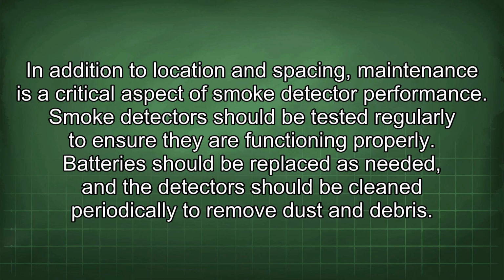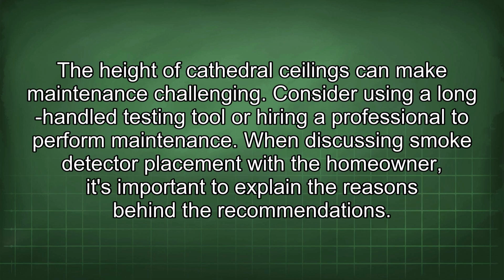In addition to location and spacing, maintenance is a critical aspect of smoke detector performance. Smoke detectors should be tested regularly to ensure they are functioning properly. Batteries should be replaced as needed, and the detectors should be cleaned periodically to remove dust and debris. The height of cathedral ceilings can make maintenance challenging. Consider using a long-handled testing tool or hiring a professional to perform maintenance.